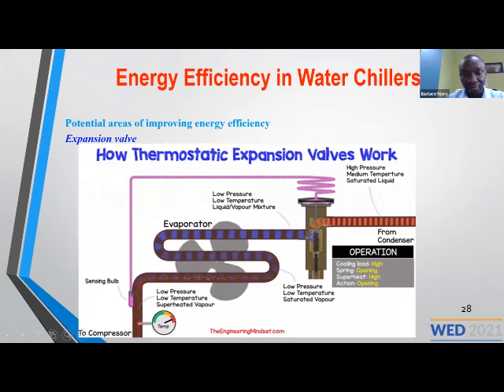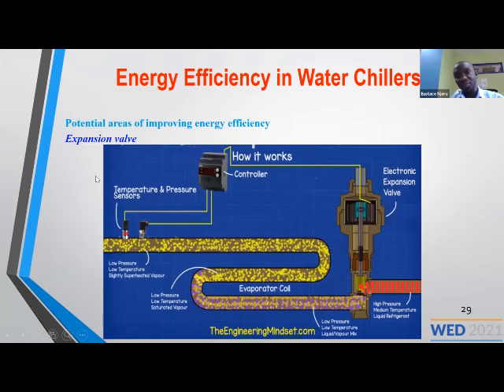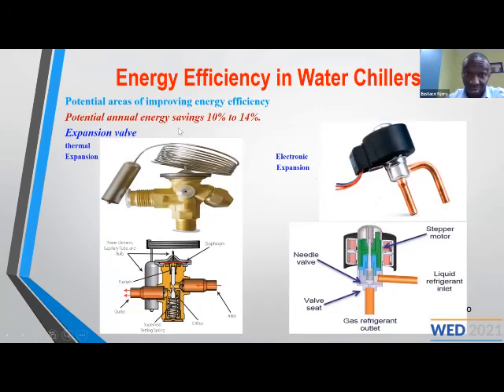So in such a case, if you find they are currently using the thermal expansion valve, it's better to retrofit it with the electronic expansion valve. And with that one you can save around 10 to 14% of the annual energy. This is the thermal expansion valve. This is the electronic valve. This is a step motor.